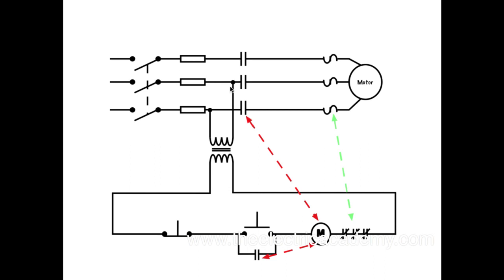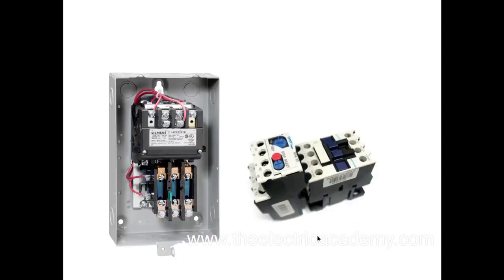That's how we close these contacts. If we push this down, this energizes, these close, and the actual motor starts. Now I cannot stress enough: this is the motor, this is the M coil. At the same time we have a set of auxiliary contacts for the control circuit so we can hold it in. When I let go of this push button, this will still run.